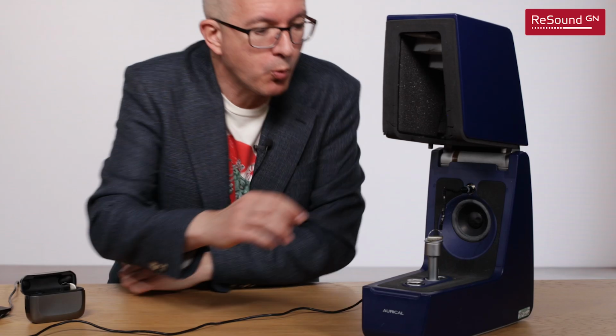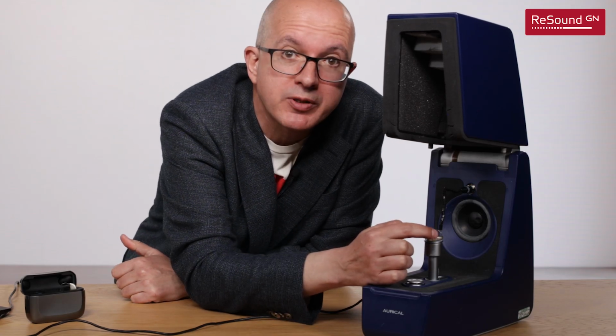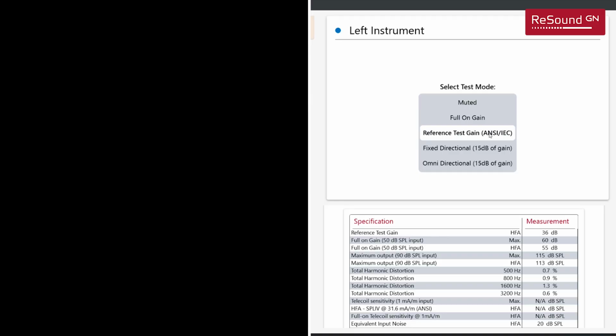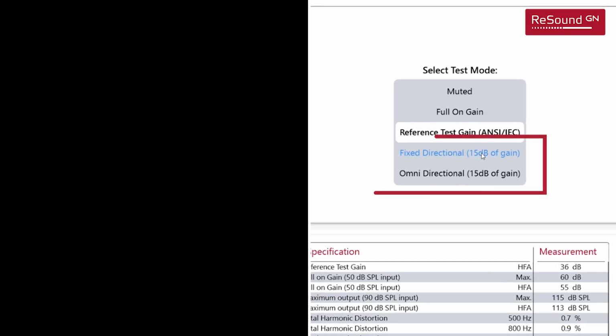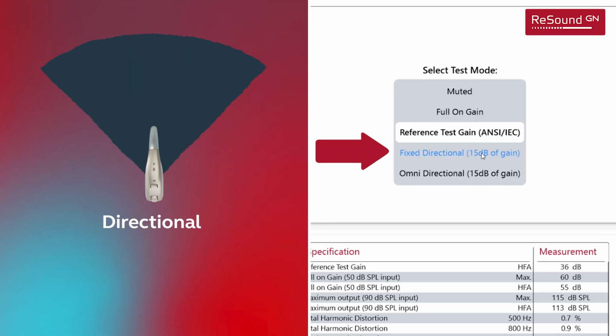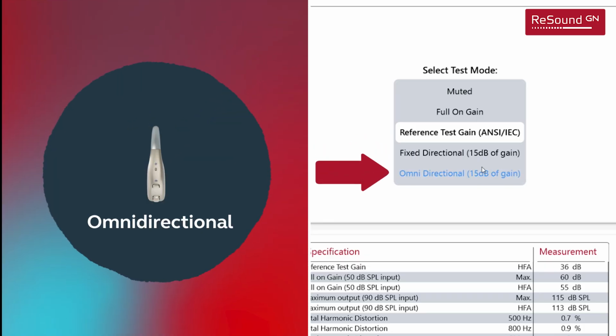But there is more, because many clinics are now incorporating directionality tests to make sure that the directional microphones of the hearing aids are working properly. This is not something you could easily do before, and the only way to do it was to manually change the programs of the hearing aids. Well, not anymore, because ReSound is introducing for the first time a directionality test directly from the test menu. Now you can easily switch between a fixed directional setting or omnidirectional while testing with your test box, which will also save you lots of time.